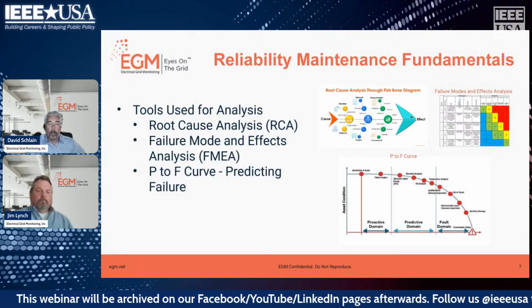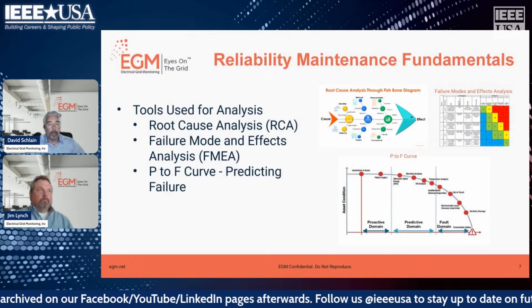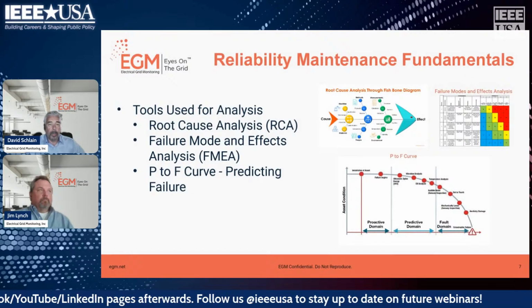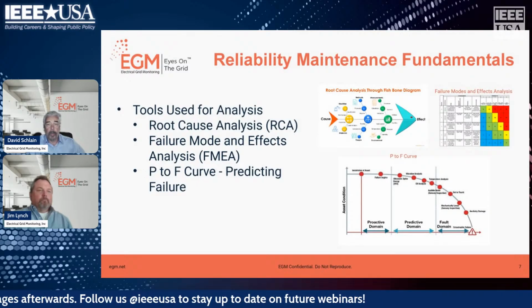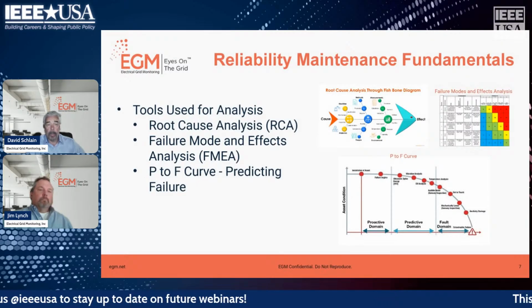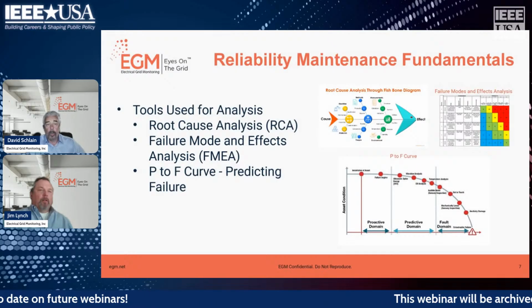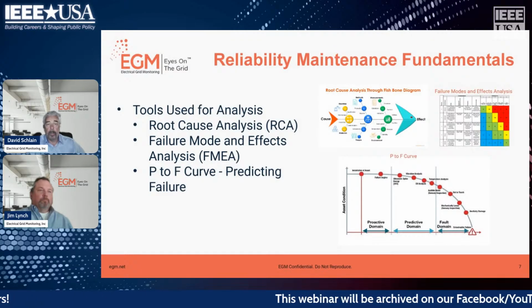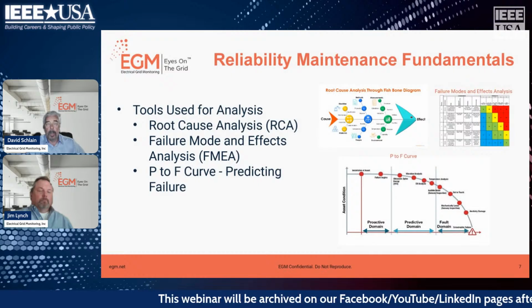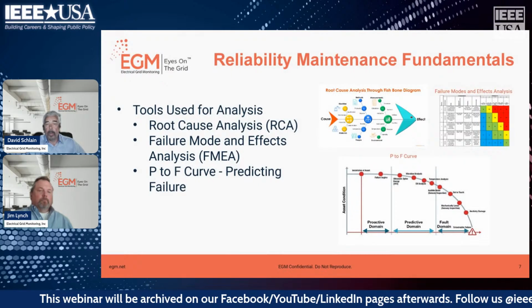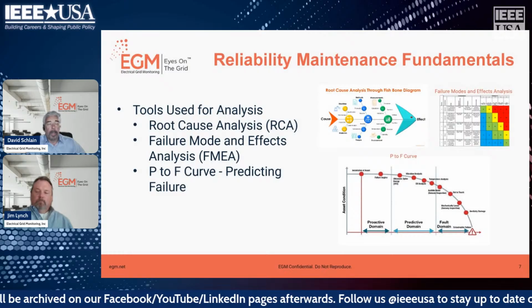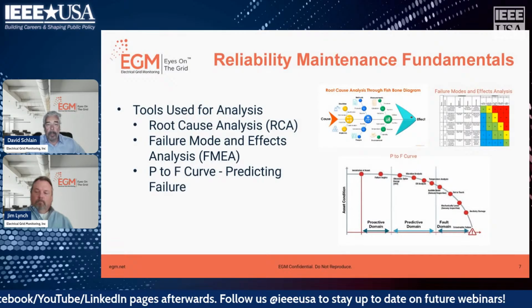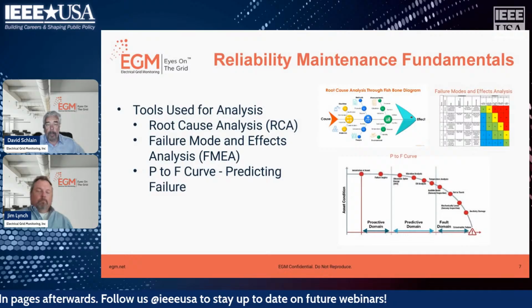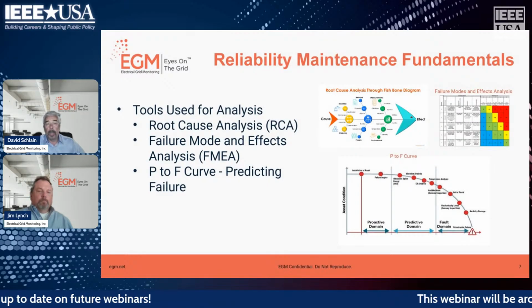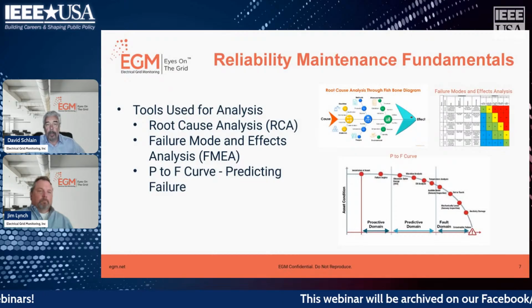Similar to rotating equipment such as motors or turbines, you can apply several sensors to help determine when that motor is going to fail. As I said before, vibration analysis and heat analysis are two very important sensing technologies applied to rotating equipment. As vibration increases or increments, that indicates the motor is probably more likely to fail. By experience in applying AI and machine learning principles, you can get a good idea of when that rotating equipment is going to fail.